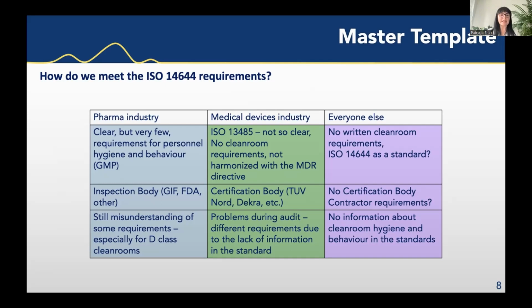Yeah, it's quite easy, let's say, to implement those requirements. Of course, when we talk about clean rooms in non-sterile drugs, it means that they are not sterile prepared or they are not sterilized. So it's under D-class conditions, like the controlled areas or areas where we do the viable monitoring. But for example, we don't do any non-viable monitoring, or we measure the pressure cascade, but we don't measure many other things like air changes per hour. We do not do the qualification process.